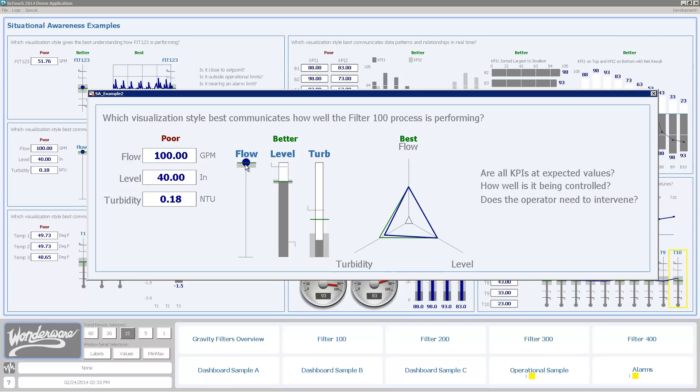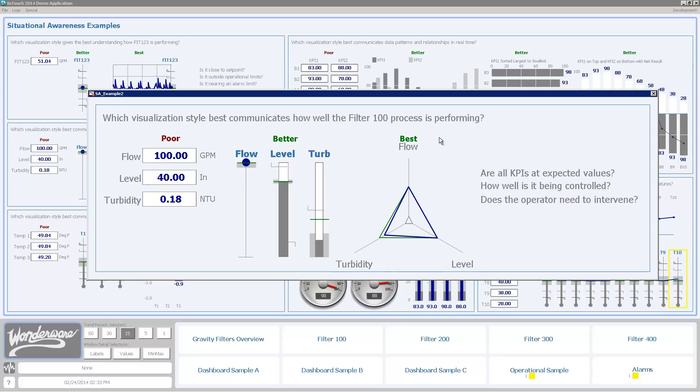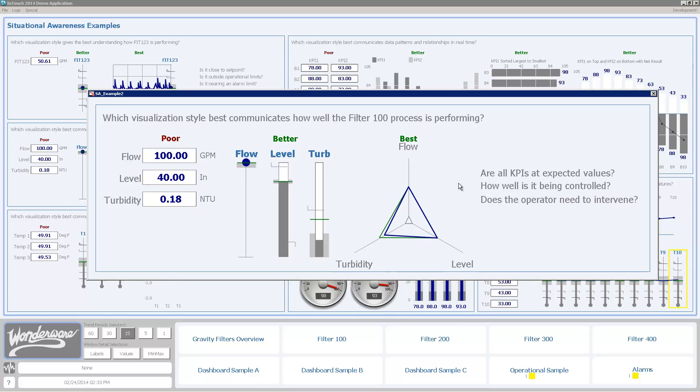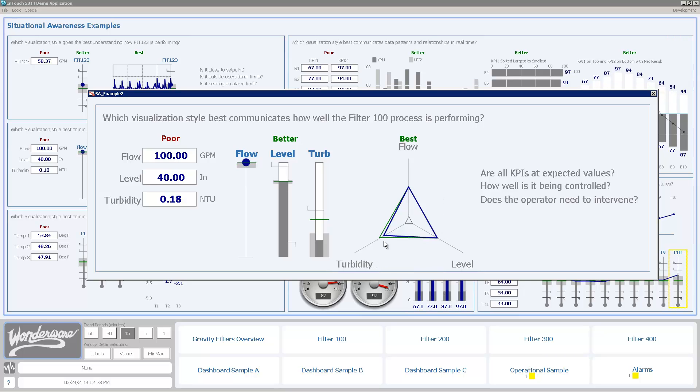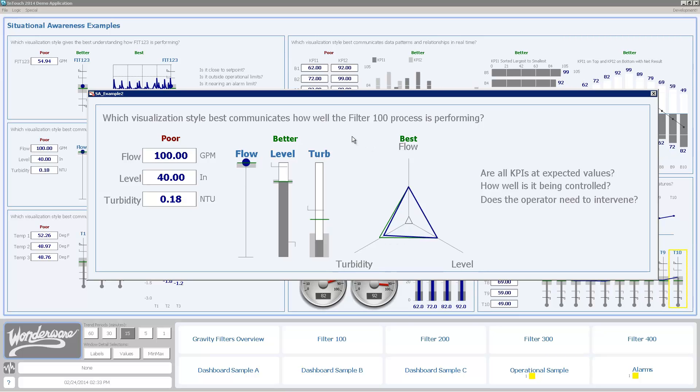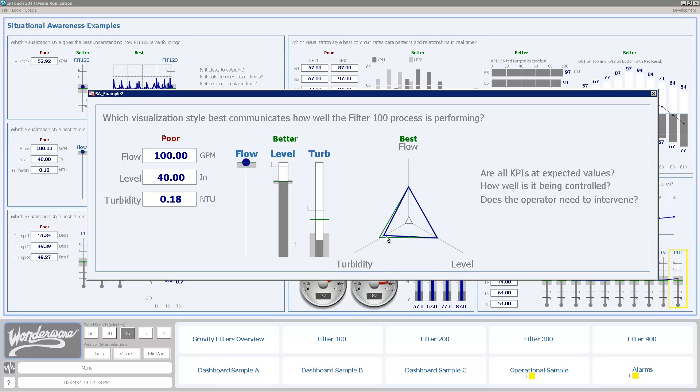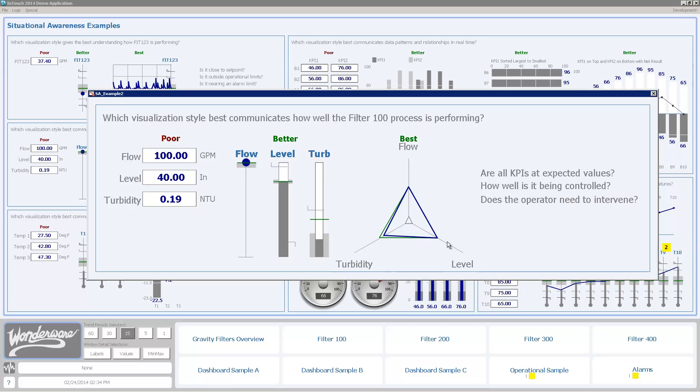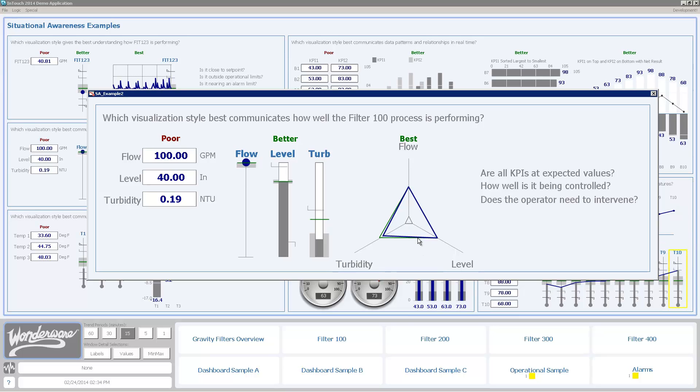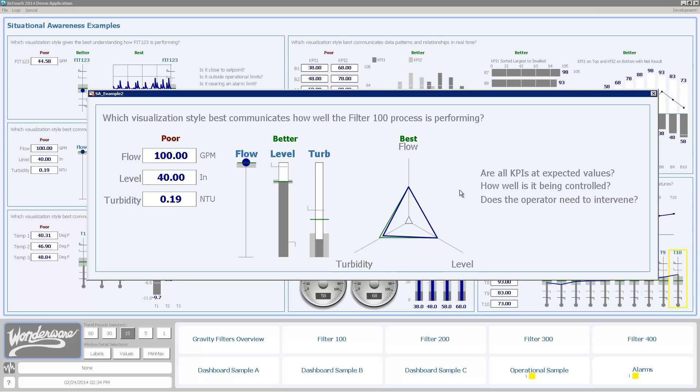But it requires me to take a little bit of time to read them individually. If I'm just trying to understand how well the process is performing, this polar star is a very effective way. I've labeled it as best, but this is somewhat subjective as to whether the meters or the polar star is best. But one thing that can be said is it's really quickly able to assess that the blue line is where I am now and the green line is where optimal is. I can see that my turbidity is actually a little bit lower than optimal, and in the case of turbidity of water, that's good. So I can see are the KPIs at expected values? How well is it being controlled? I'm doing a pretty good job. Does the operator need to intervene? In this particular case, the answer is clearly no.